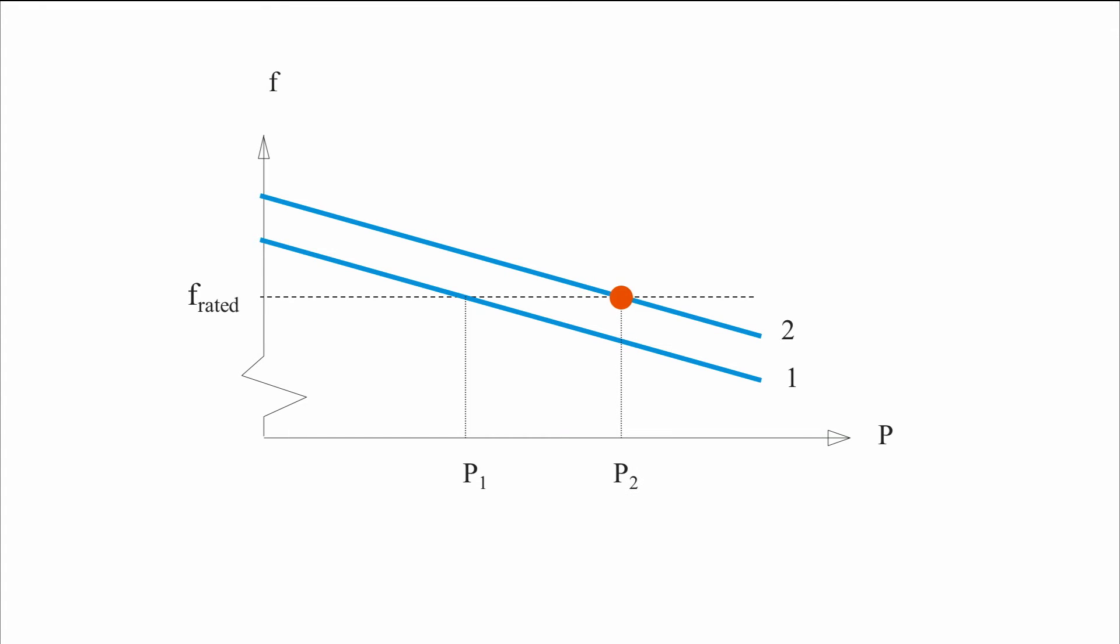Secondary control brings back the system to the original frequency by increasing temporarily the prime mover. This raises the kinetic energy, and therefore the frequency. It also allows to bring the tie-line exchange of power back to the one that was agreed between the areas. An area can be a country, for example.